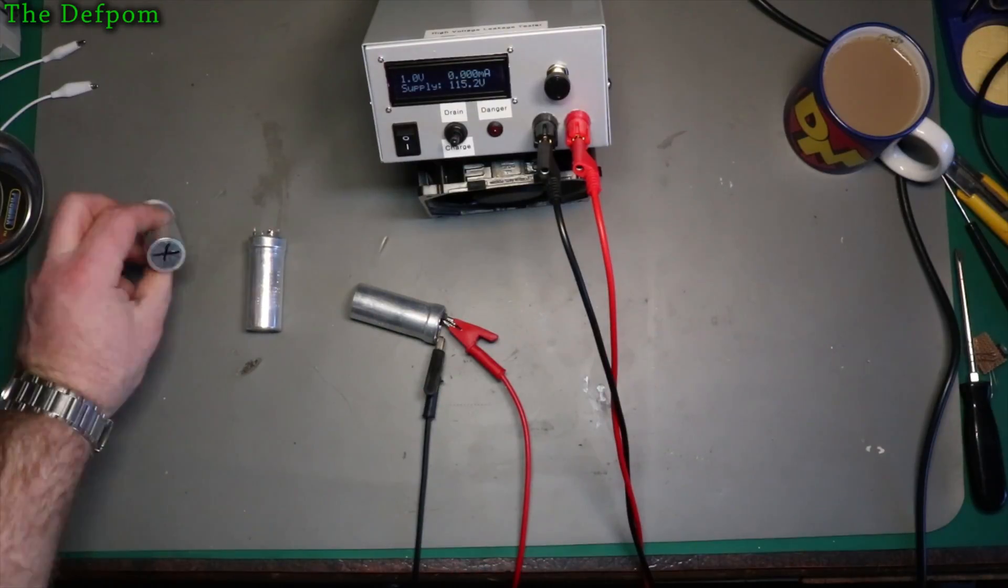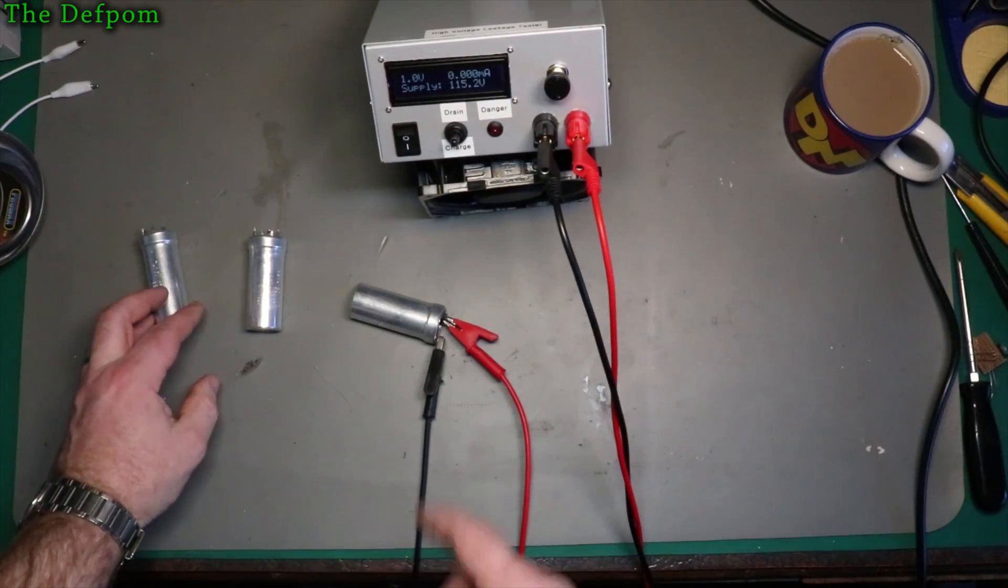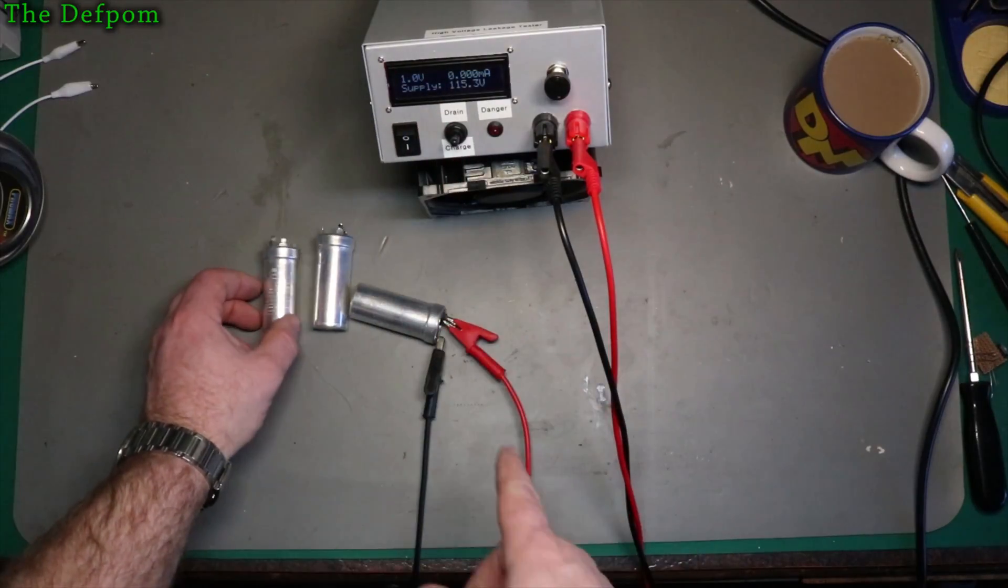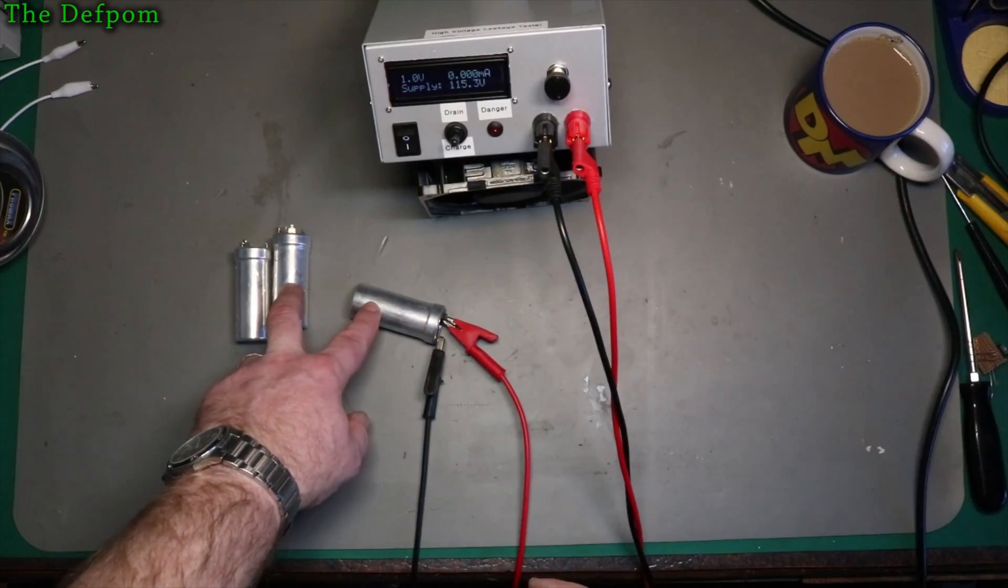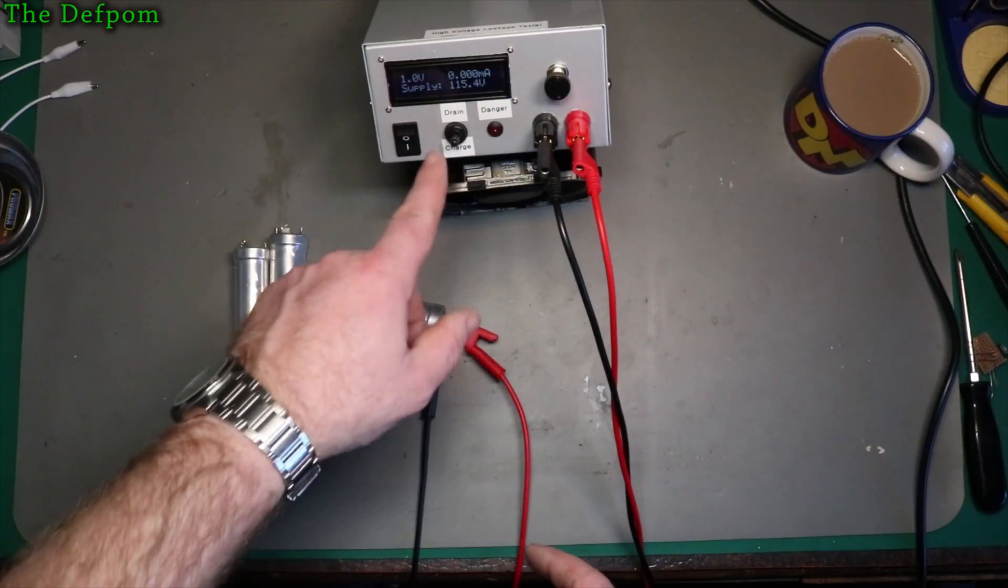And this is the cap which was bad, which is what it's got next on it. I just want to see how they come out on the leakage tester to see what kind of result you actually get from the tester. Now these two caps tested okay on my other units, so we'll see what this thinks of it.